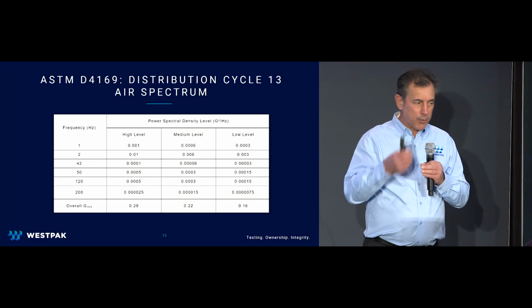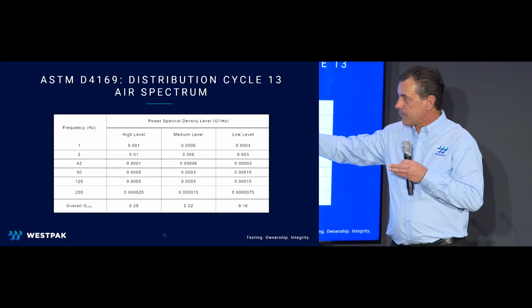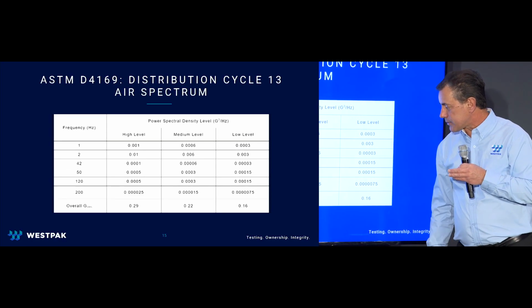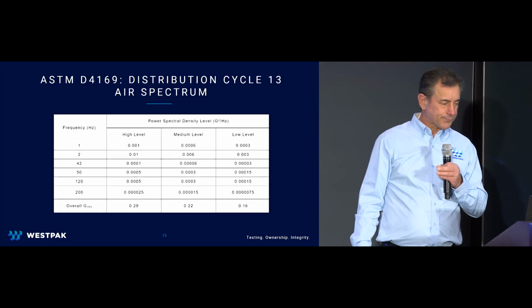And these are the breakpoints. So not that you need to memorize these. These are in the standards. And you have low, medium, and high levels. And those are the overall GRMS from the standard.